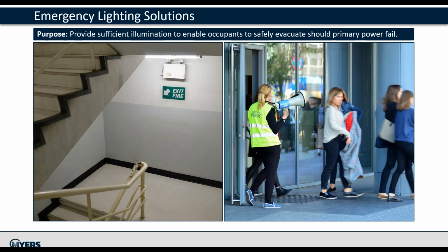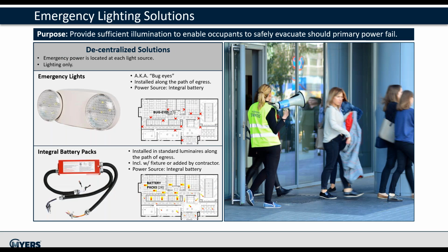The next slide covers two different types of emergency lighting solutions. There are two different classifications and two products within each classification. The first classification is decentralized solution that consists of unit equipment, commonly referred to as bug eyes, and integral or remote battery packs. Unit equipment is installed along the path of egress as shown in the diagram and normally is powered off. When the utility power fails, it's powered from a small self-contained battery.